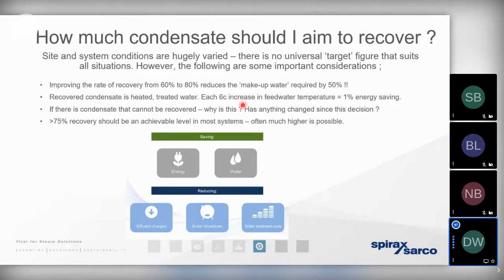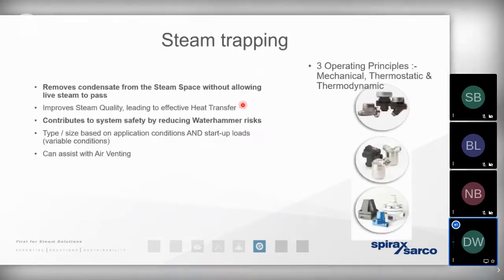So in the last presentation we went through 2 weeks ago, we understood that it's the steam trap that really separates the steam distribution network from the condensate return network. And the steam trap is a passive device. In other words, we need a good steam pressure, both in the process and in the distribution pipework, to push the condensate across the trap and to give the condensate enough motive energy to return back to the boiler house.